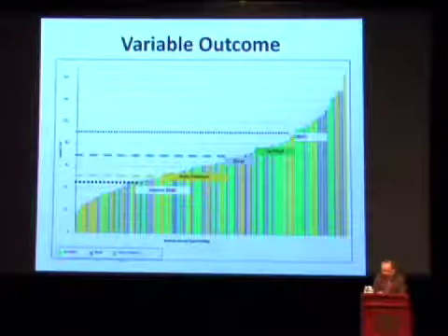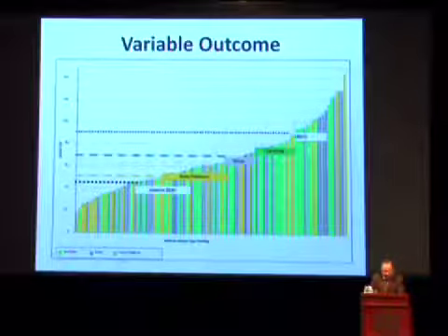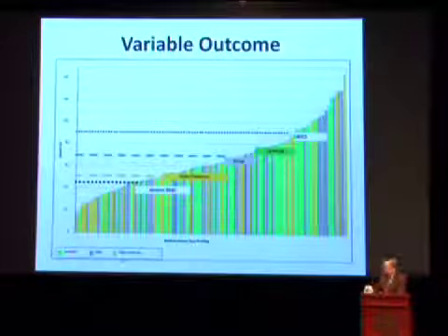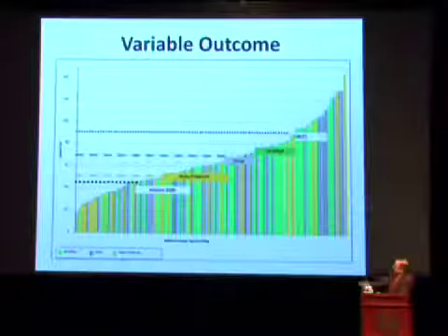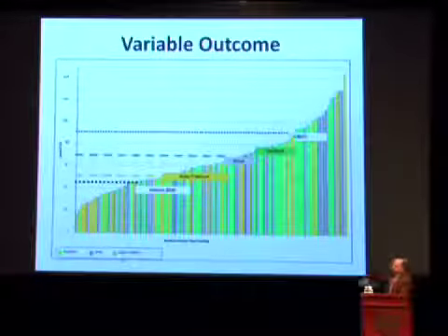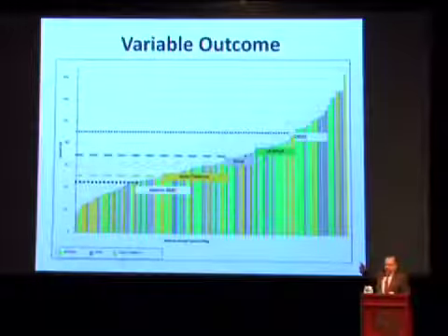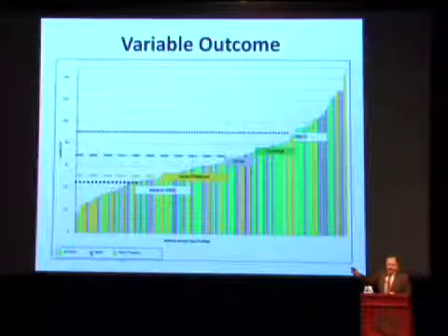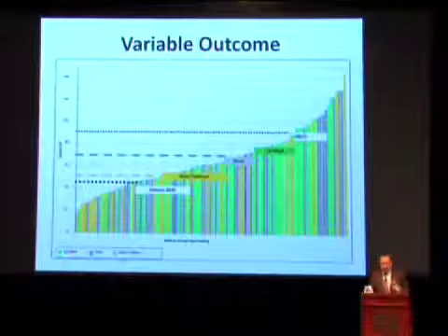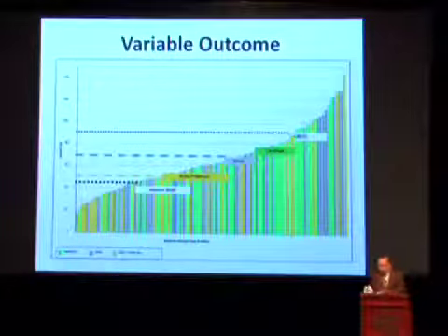So my firm, me and a coworker actually, did a study about 2 years ago of the actual energy performance of buildings that had been rated as LEED buildings. And this is the data. On this axis is energy use, and these are all the buildings in our study. And you can see there's quite a range, and this is a subset of buildings that are defined as typical energy users. This doesn't include medical, lab, et cetera buildings, which use way, way more energy. The point is that energy use in buildings is highly variable in all buildings. It's highly variable in every building in this city. I'll talk about that more in a minute.